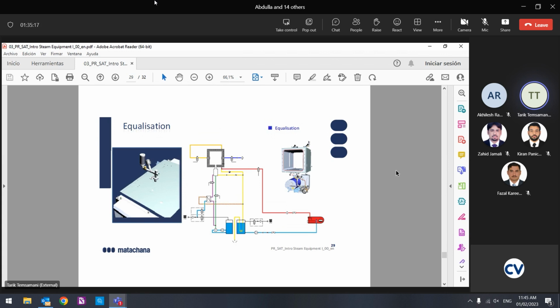Bacteria. Why? After sterilization, the material is sterile and I put bad quality of air to the load. This is the antibacterial filter. So this filter removes everything from the air, and once I put the air in the load, this air has to be clean. So if I didn't change that, everything I do is wasted.